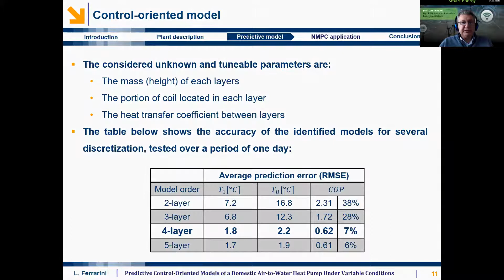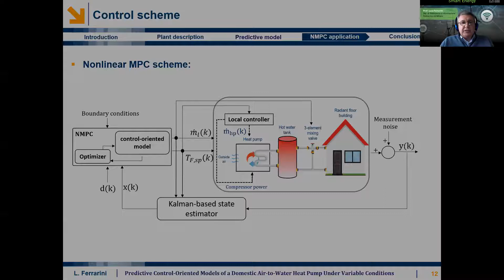So we set up a control problem, an optimal control problem. So we have our reference model, our detailed model of the system. And then we set up our controller. The controller is based on an estimator, a Kalman filter-based estimator. And then we have a control-oriented model, which is a simplified model of the whole system. So the reference model has actually the mass flows and the temperatures and the stratification of temperature and the heat inside the tank, all of that, while the control-oriented model has a simple tank model and a simple COP model. So that's the challenge: if our model inside the controller is fair enough to control the system and simple enough to be implemented in real time.